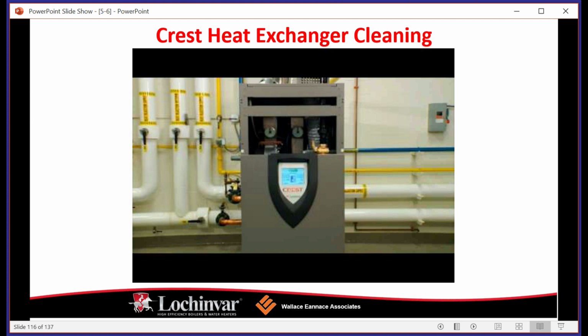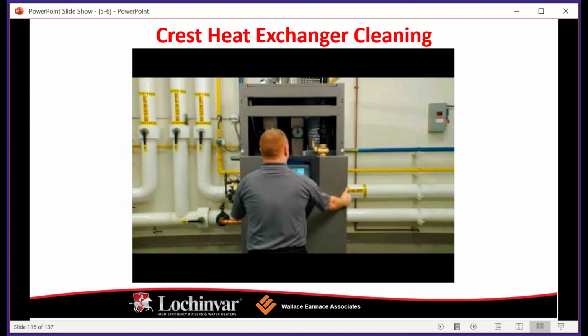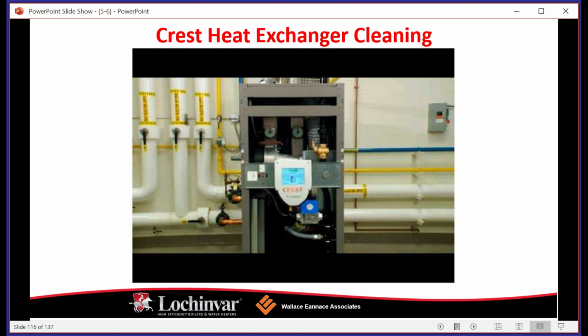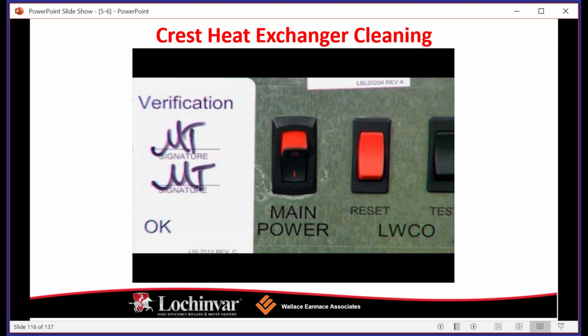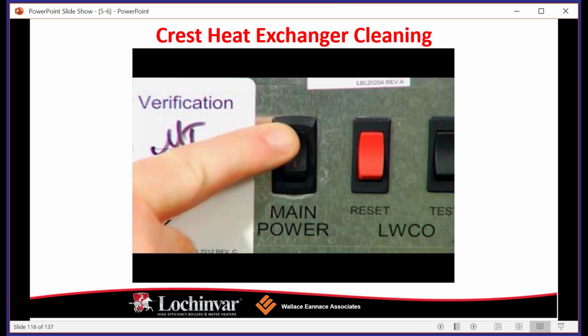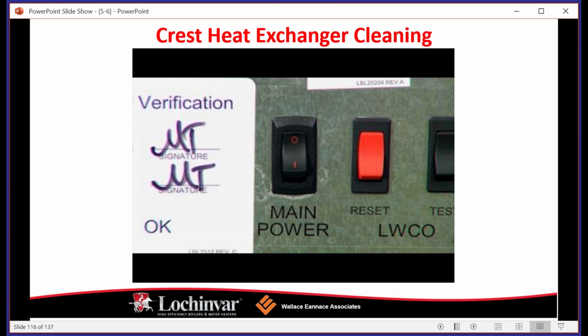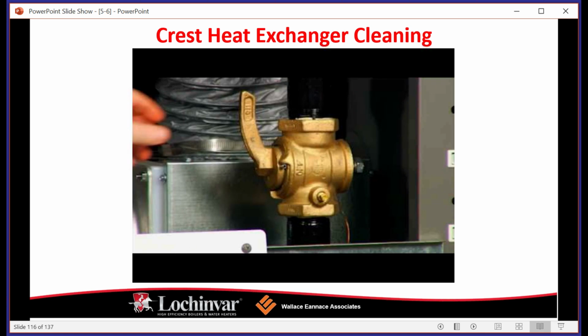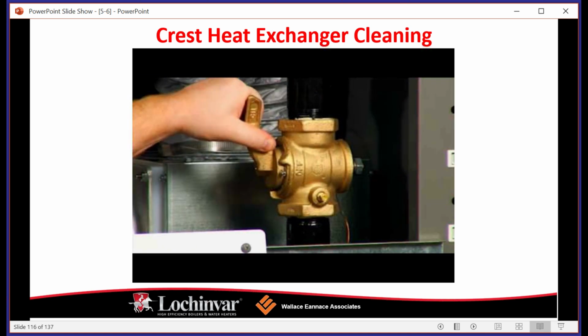And again, a lot of people will tell you a lot of different things, right? So if the flame is too orange, it's too fuel rich. If it's too blue, it's too oxygen rich. So you want to be somewhere in the middle. The best way to do this is to verify that with a combustion analyzer, which we're going to talk about a little bit too. So again, you're going to check your flame signal.